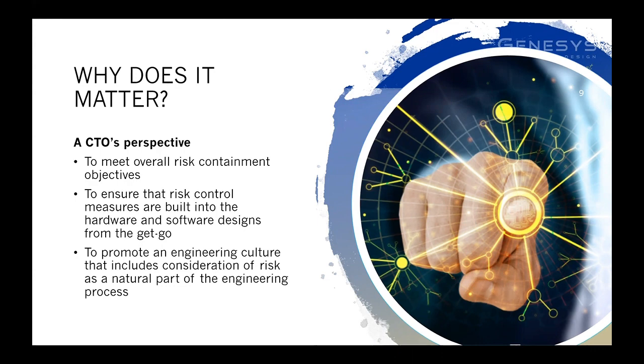One technique that we use quite regularly is to use a state machine based PLD or FPGA device to control critical interactions, then have that operating in parallel with a microcontroller that does the higher level control function, but the underlying state machine will prevent that software from doing anything crazy. So you have a redundant control system that builds in risk containment.